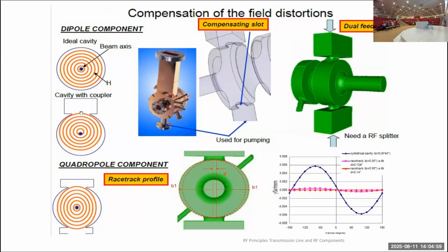When the electron beam, which is going to be accelerated by this field, passes through this cavity, it is also deflected on one side, and our beam doesn't remain aligned with the rest of the structure, and we can't get the proper acceleration and proper hitting of the beam on the target. So we can eliminate this skew by changing the dimension of that coupling cavity.